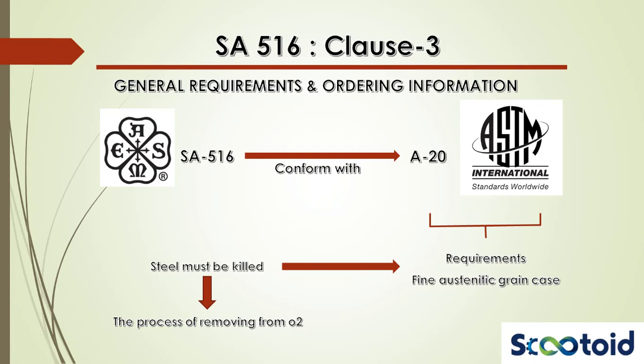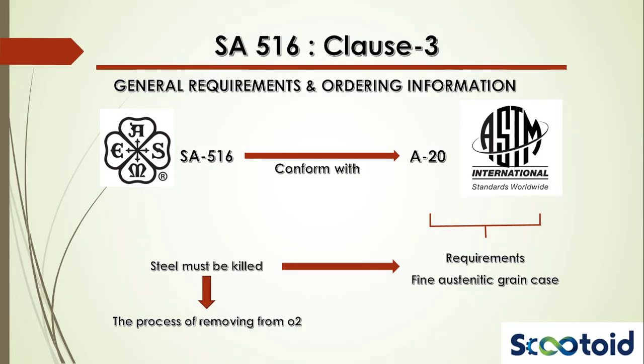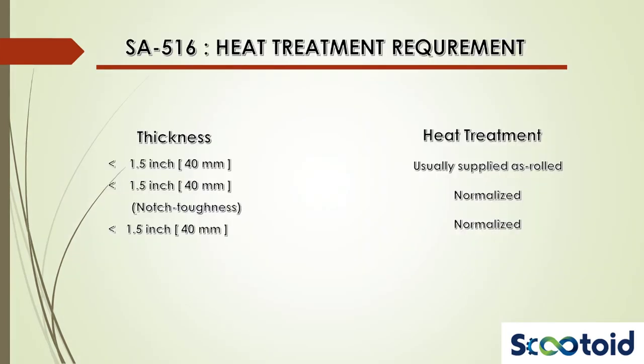The clause 'Materials and Manufacture' covers the steelmaking practice. It includes a very important point that the plate manufactured under the SA 516 specification needs to be killed and should conform to the fine austenitic grain size requirement of the specification A20 from the ASTM. In steelmaking, killing refers to the procedure where free oxygen is removed from the material.